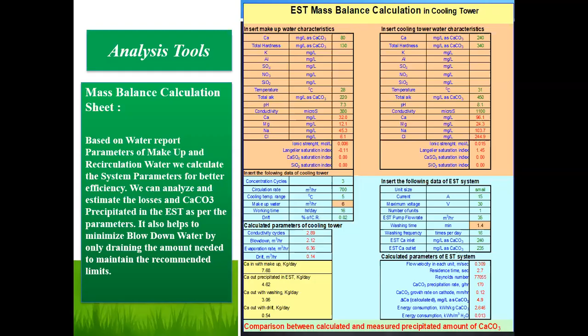So here is the depiction of that. The water from the cooling tower is coming, right? So from the makeup, based on that previous calculation only, this picture has come up. In the makeup water per day, it was coming near about 7.68 kg. The calcium which is being precipitated in the EST was near about 4, and what went out with washing during the blowdown was 3 kg per day.